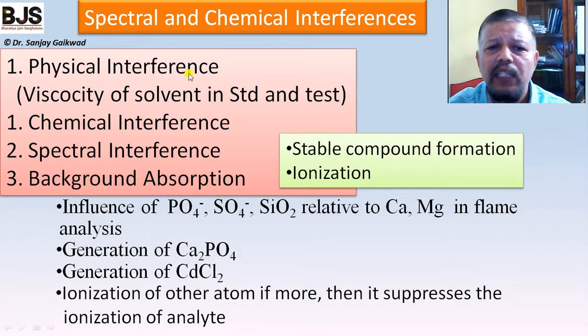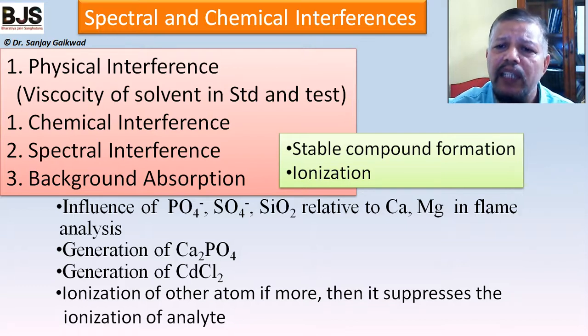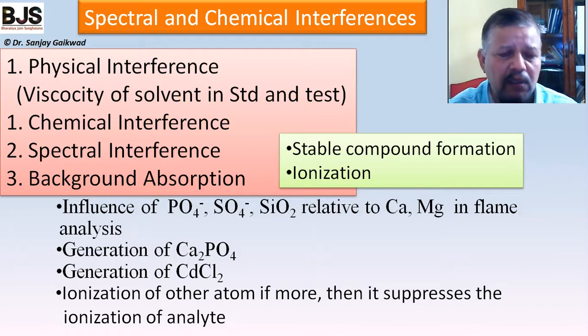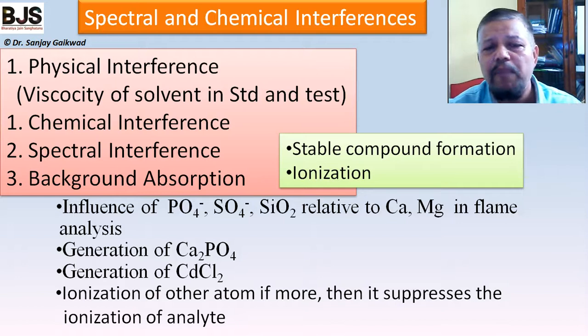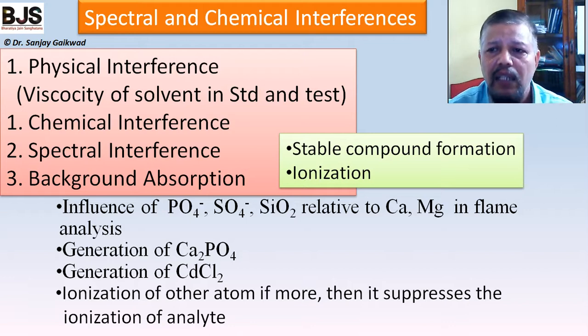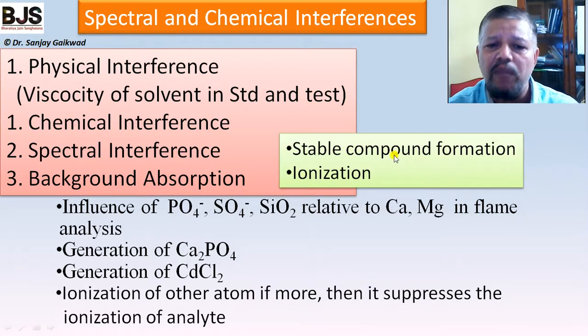There are several interferences in AAS: physical interference, chemical interference, spectral interference, and background absorption. Physical interference occurs when different solvents are used for standard and test solutions — differences in viscosity affect results. Higher concentration aqueous samples in a total consumption burner also affect flame temperature, causing physical interference. Chemical interference occurs when ions form stable compounds that are not easily transferred into the flame and remain as precipitate in solution.